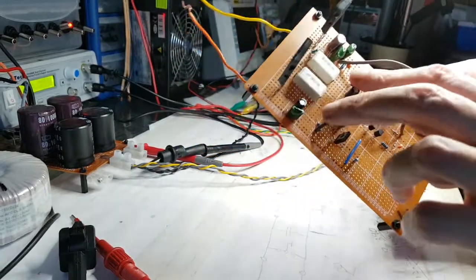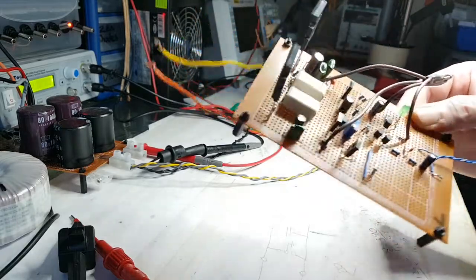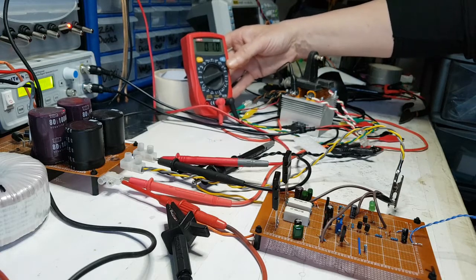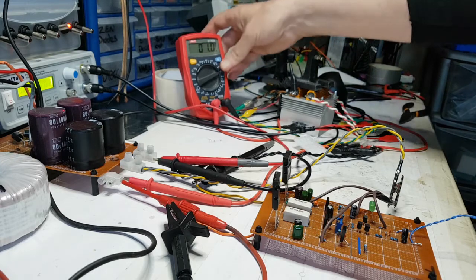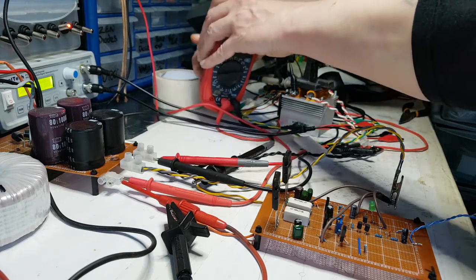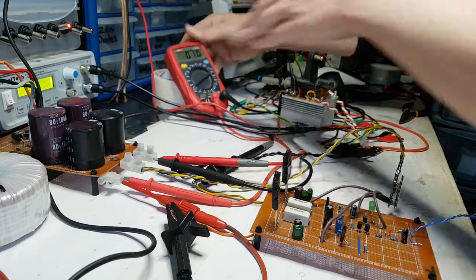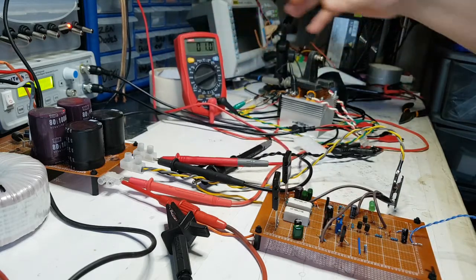transistors in, got 2 new drivers in, and let's just give that a little bit of a check and see what happens. Okay, well that's a nice sign. But it's not shorting out to 0. I don't know if you can see that on one. It's not shorting down to 0, which it was, which means I've got a little bit of juice in those capacitors, and it's coming out. Just sit like that nicely, like I want you to.